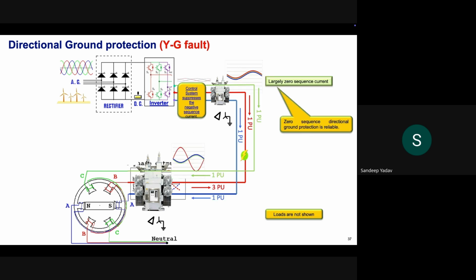This is the case of a middle phase to ground fault, or a Y to ground fault. If you look at the ground fault, we see that the response from a synchronous machine is that the current in the faulty phase has risen from 1 per unit to 3 per unit. However, in the healthy phases, the current is still 1 per unit.